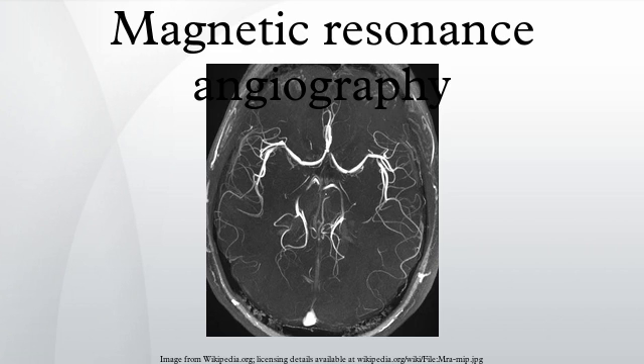Traditional MRA suppresses signals originating from body fat during the actual image acquisition, which is a method sensitive to small deviations in the magnetic and electromagnetic fields and as a result may show insufficient fat suppression in some areas. M-Dixon methods can distinguish and accurately separate image signals created by fat or water. By using the water images for MRA scans, virtually no body fat is seen so that no subtraction masks are needed for high quality arteriograms or venograms.